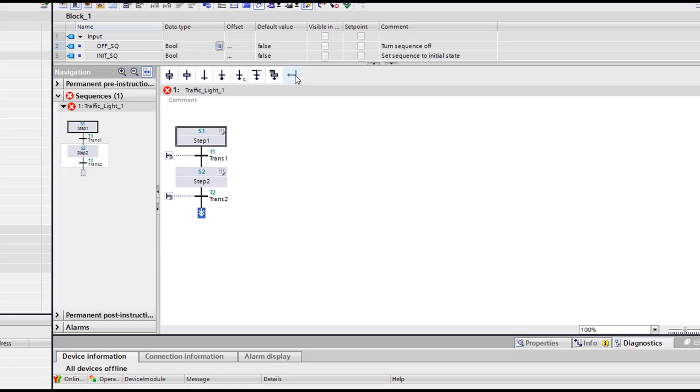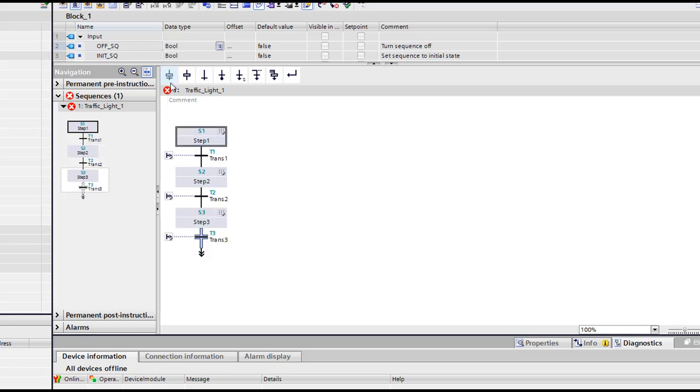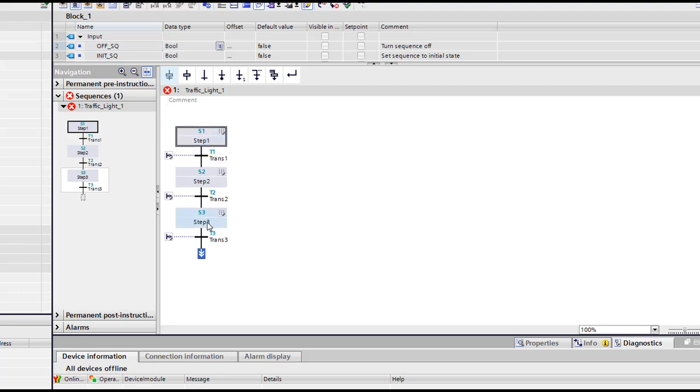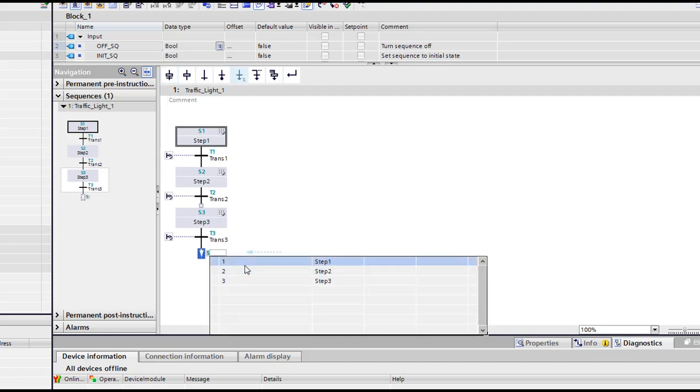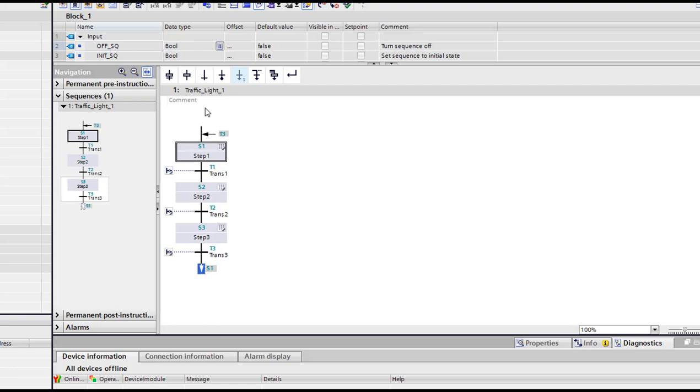If I want just to add one or open a branch, I can press this. And sure you cannot do transition after a transition, or a step after a step. A step always should be followed by a transition. I'm gonna add another one. So here but if I leave my sequence like here, it's an error. I should always jump this transition, after that should be back to another step or from a step to another transition. So here I'm gonna jump it to step one, and as you will see the error symbol is gone.